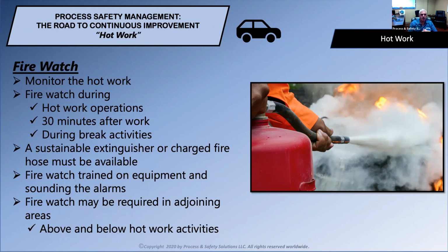A suitable fire extinguisher or charged fire hose must be available. The Firewatch must be trained on the equipment, and this is an important one as well, sounding the alarms, making sure that they know how to sound the alarm. Many times in our interviews doing compliance audits, we specifically ask that question: do you know how to sound the alarm? Oftentimes what we hear is, well, I would pull the fire alarm. Well, where is that fire alarm? I don't know. So if they don't know where those specific items are or how to sound those alarms, then they haven't met the requirement or have not been trained properly in hot work.